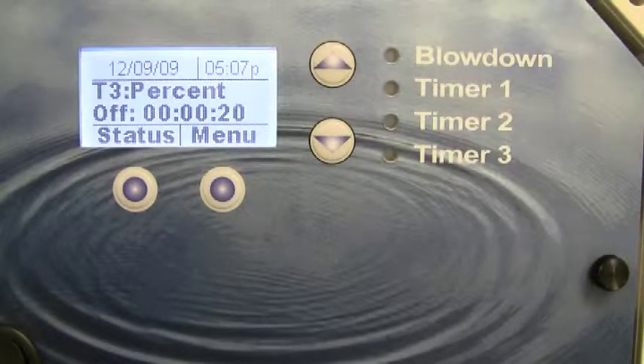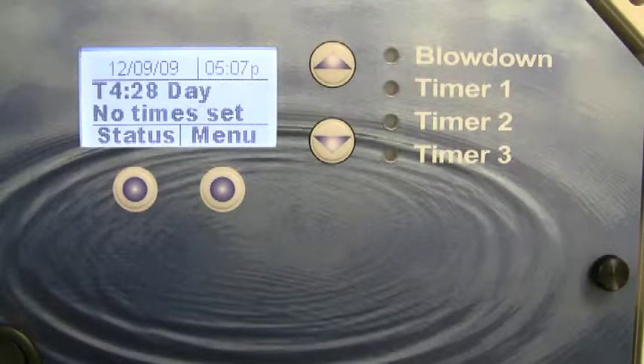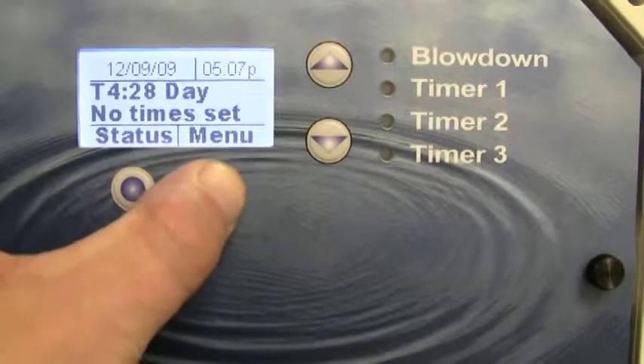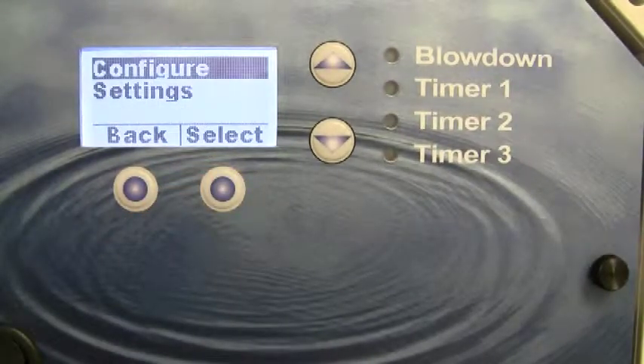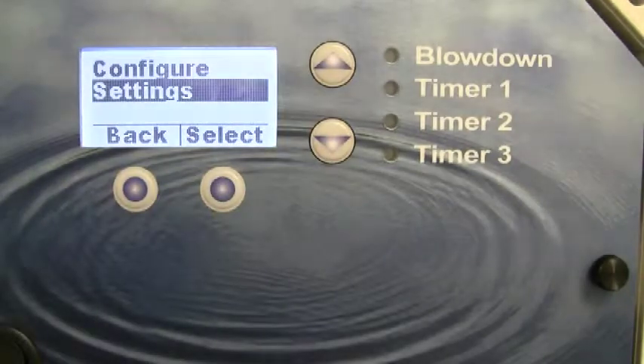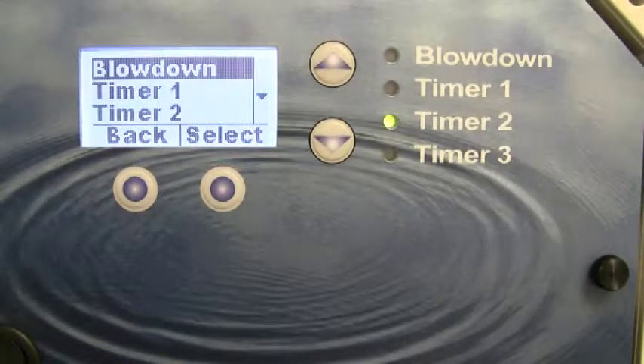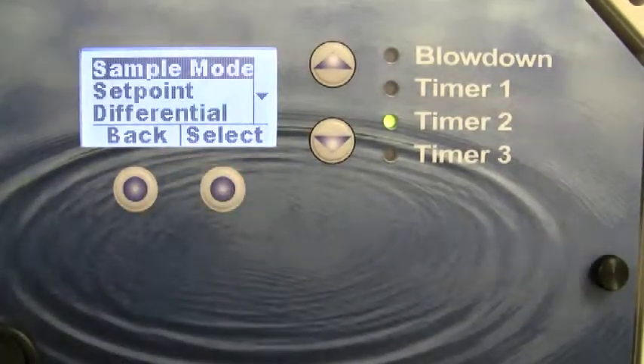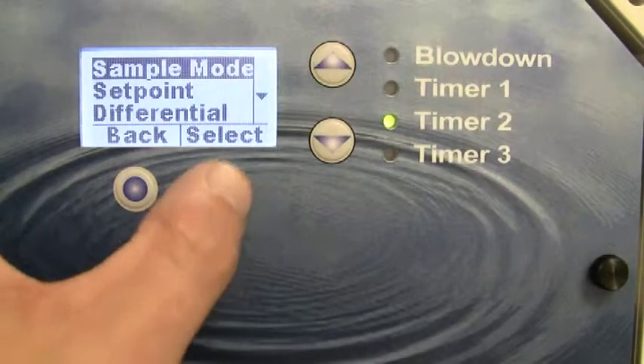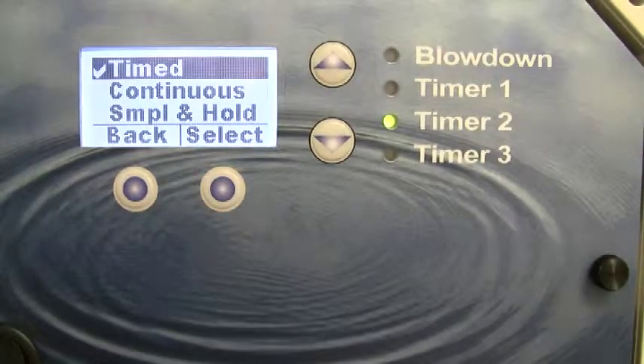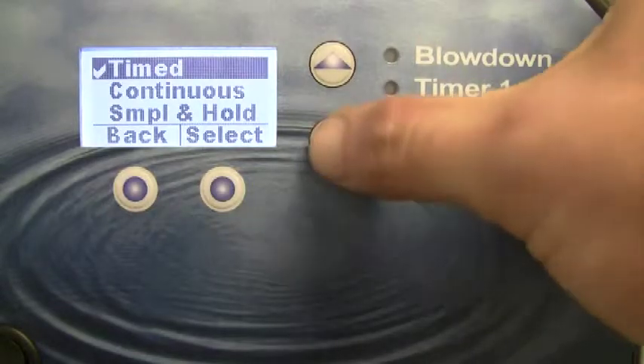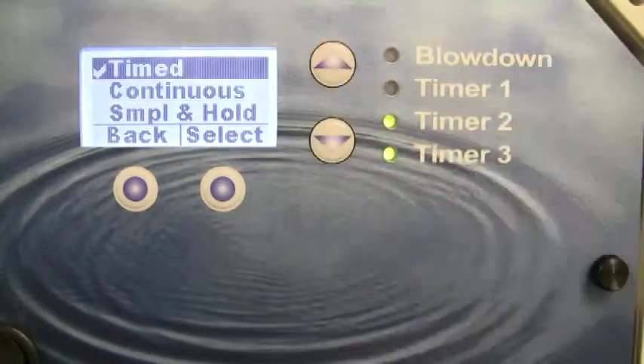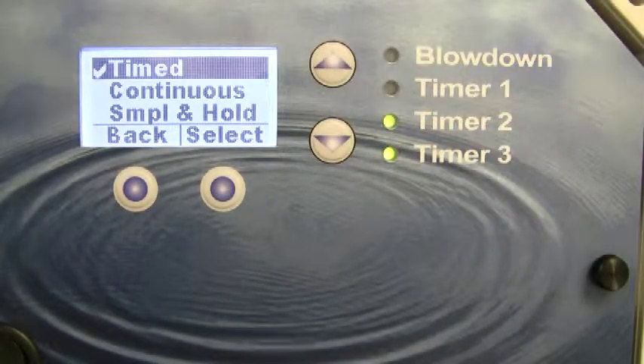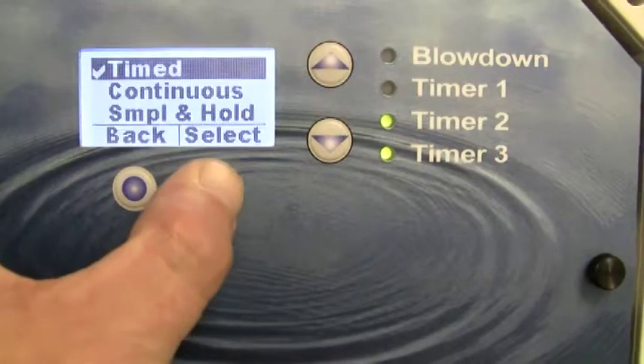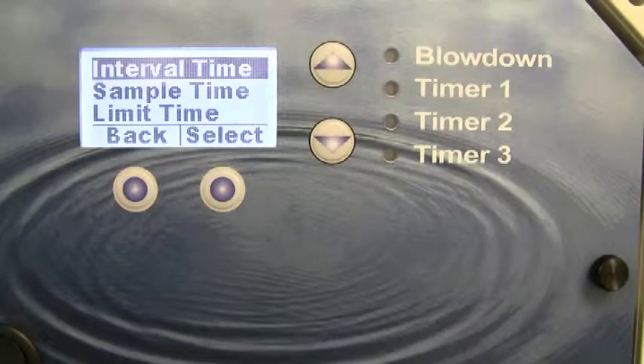If you would like to change the default settings for the time sample mode, simply press the menu key from the main menu. Next, enter the settings menu. Then enter the blowdown menu. Enter sample mode. Here you can change the type of mode that the controller is operating in if you wish, or you can press select at time mode and it will give you the settings for the time sample mode.